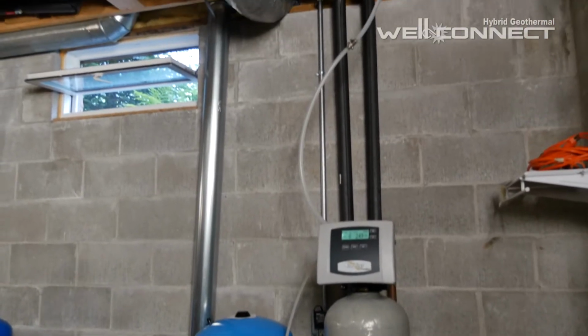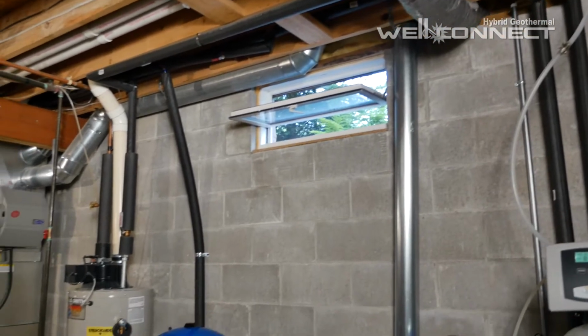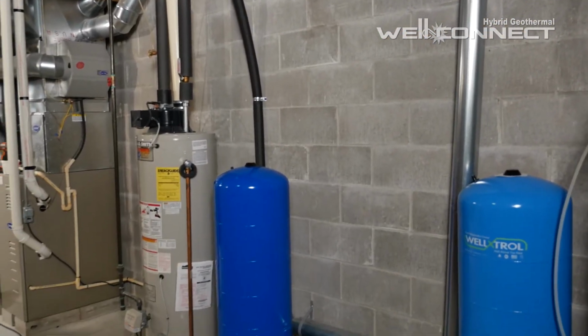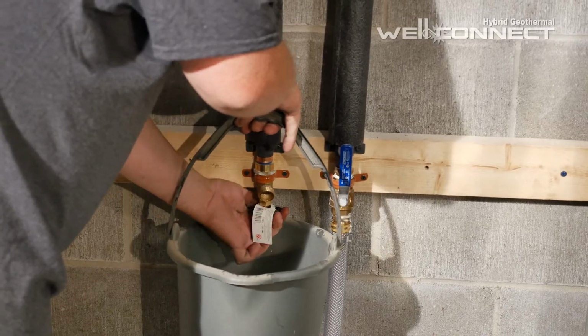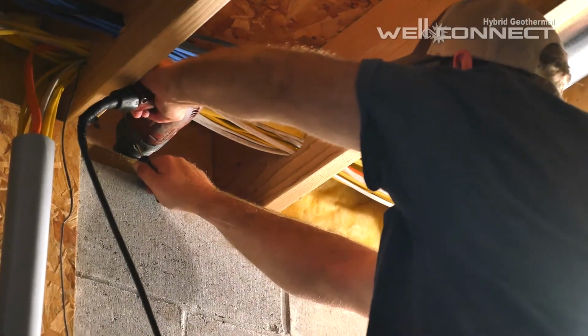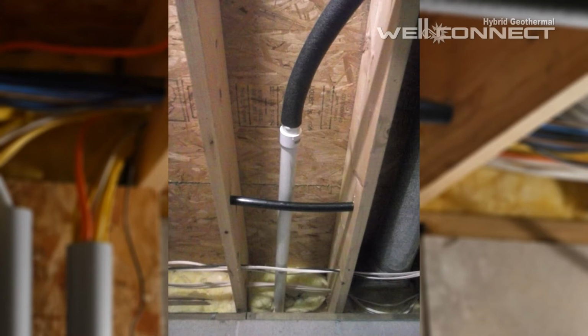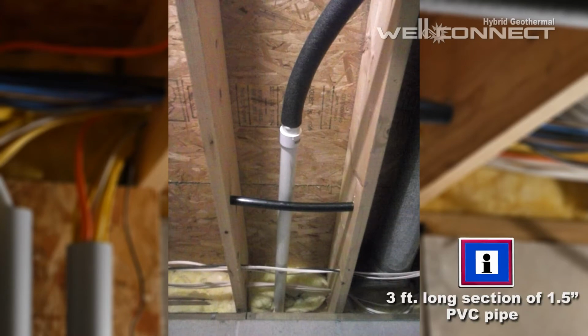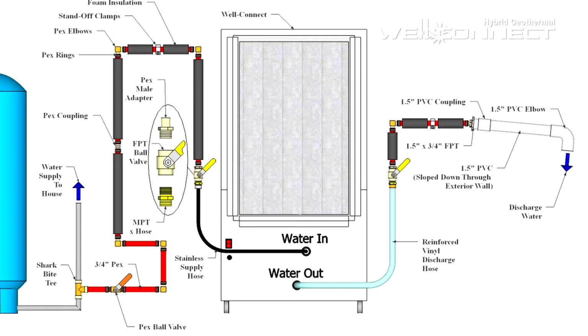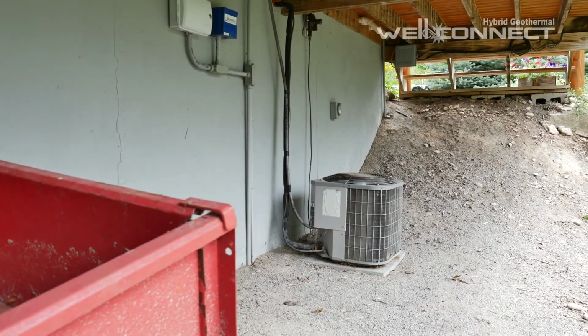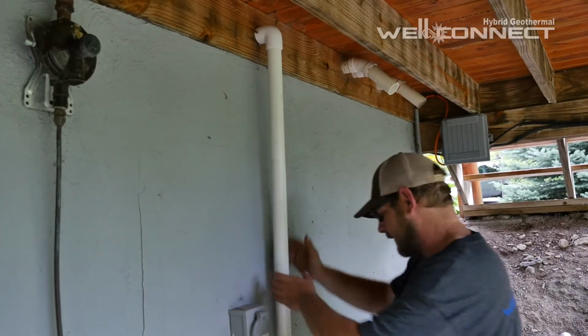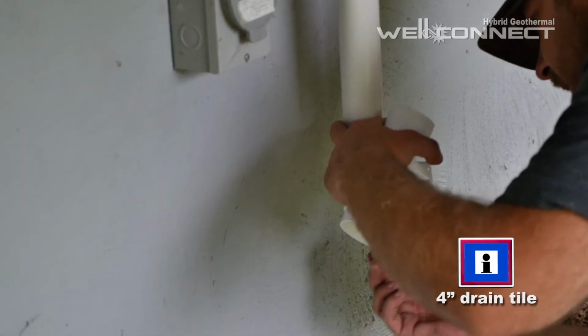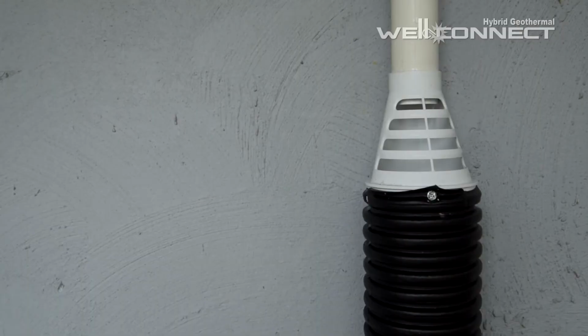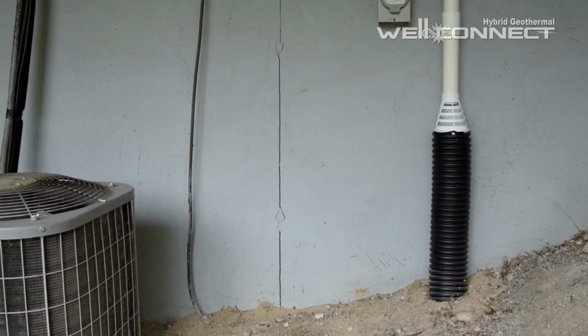To accommodate the discharge water leaving the WellConnect, a second insulated 3/4 inch pipe must be run with a shut-off valve and male hose fitting on the end near the WellConnect. This discharge water piping will exit the basement through the rim joist. The 3/4 inch pipe should transition into a 3-foot long section of 1.5 inch PVC pipe, secured with a positive downward pitch toward the outside to ensure that all water drains from the PVC pipe whenever the WellConnect shuts off. Once outside, the 1.5 inch PVC pipe should immediately turn down and discharge through the combination freeze-stop air gap fitting into a 4-inch drain tile to direct the water away from the foundation and carry it to a convenient point of discharge.